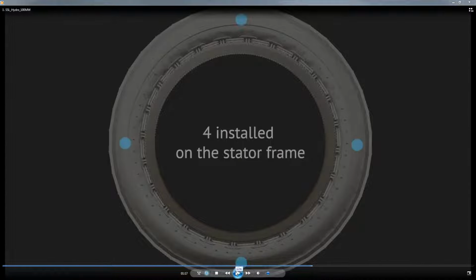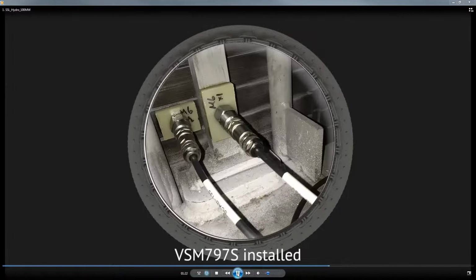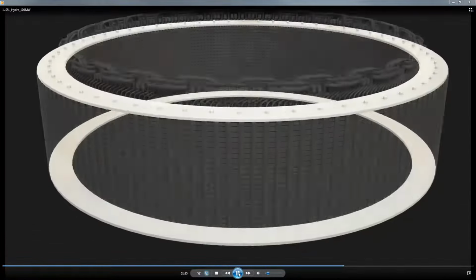Next, we have accelerometers, piezoelectric in this case, that are used to monitor the vibration, the absolute vibration, or the acceleration of the core and of the frame. So we install 4, in this case here, 4 on the frame, and we'll install 4 more on the core. And the reason for that is we want to see not only how much the core and the frame are vibrating, but whether they're vibrating in sync. Are they moving together, or is there a lag telling us that there's a looseness developing between the core and the frame? Because if that's the case, you'll start having some arcing, potentially some arcing between the core and the frame, causing severe damage. We've had quite a few cases of those. So we use those in sync to see if there's any kind of looseness.